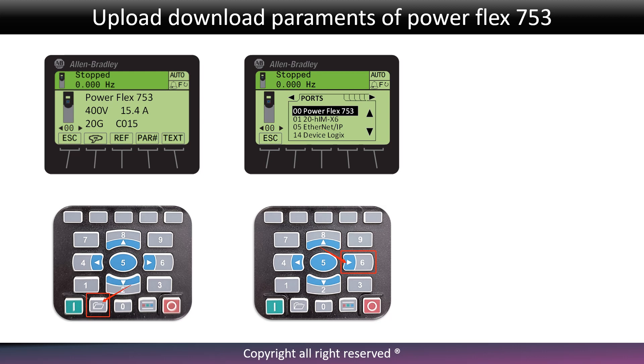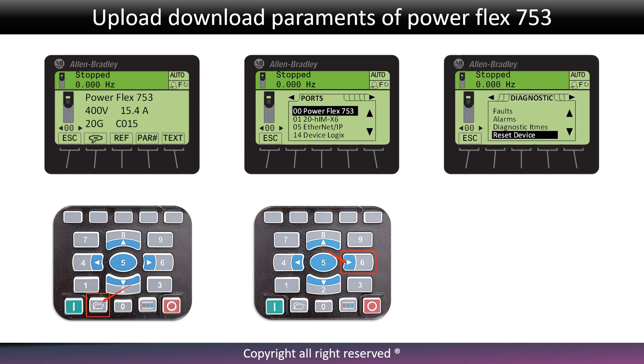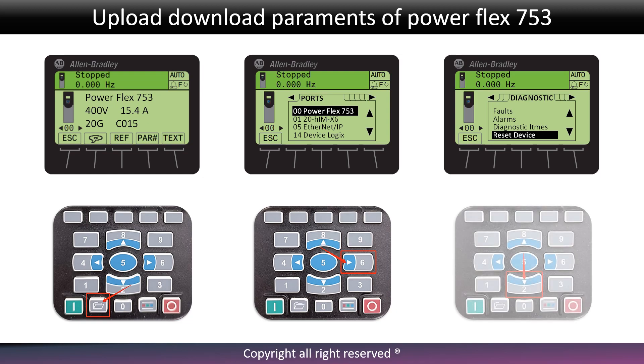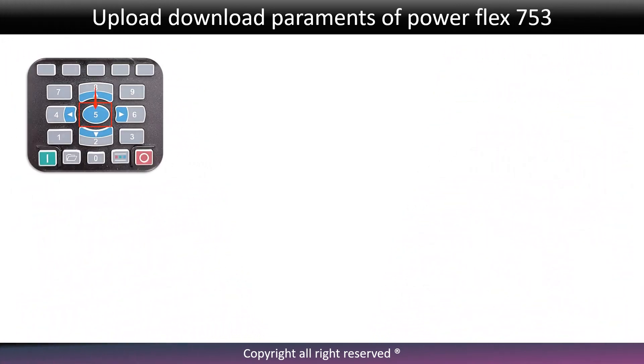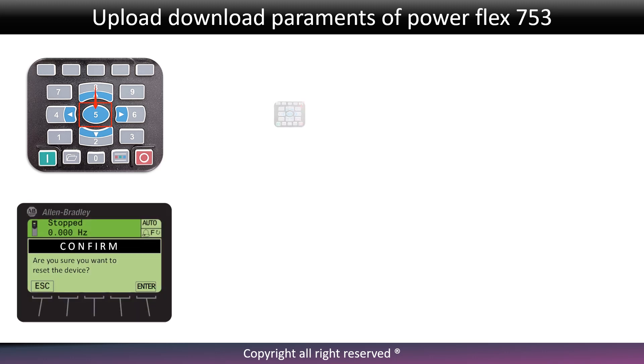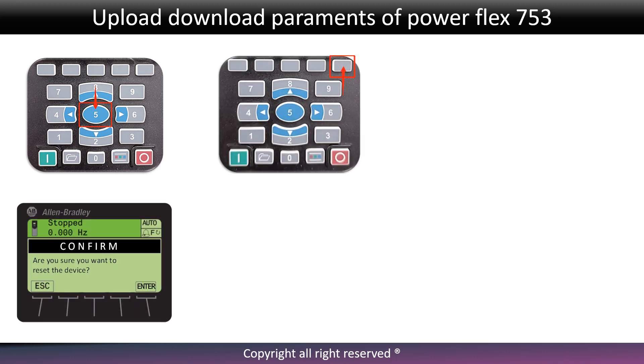Press the folder button, then the right side arrow button until the diagnostic tab displays on screen. Press the down side arrow button to select the reset device option. Press button 5 — a device reset confirmation message will display. Press enter to reset the inverter; the inverter will restart.